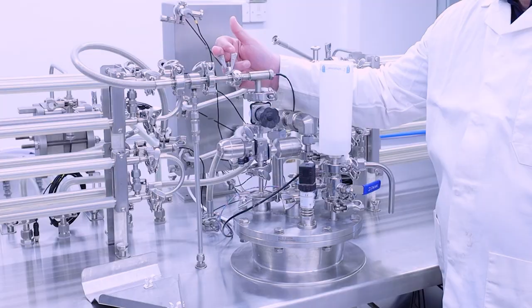The way in which this works, if you remove the protective guard, following the preheat, formulation is passed into the direct steam injection unit. Steam is directly applied to the formulation for very short periods of time. The reason for this is if you're processing something that's very, very sensitive to heat, you only want to apply heat for a very, very short period of time to avoid degradation of the formulation. Your formulation then comes down into this vessel here, which is under vacuum. The vacuum is drawn from a vacuum pump under the surface of the tabletop, and that allows any moisture from the formulation due to DSI to be removed.